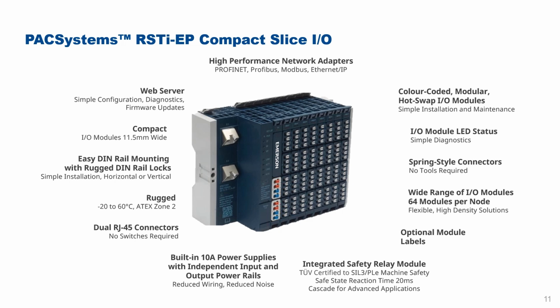We also have Profibus, Modbus and Ethernet IP as options, allowing this I/O to be used inside other systems beyond the use of standard Emerson controllers. There's a wide choice of modules with up to 64 modules per node, and with these modules we have very good diagnostics and maintenance capabilities with color-coded hot swap I/O modules, LED status on the modules themselves.